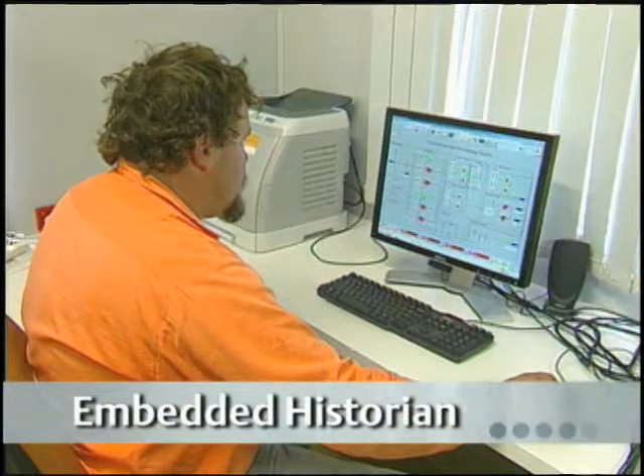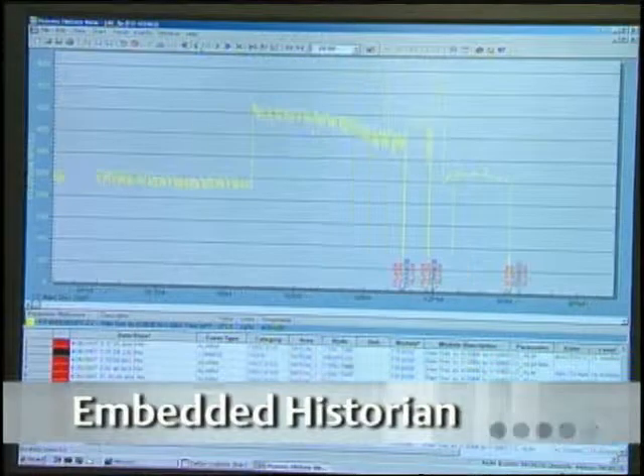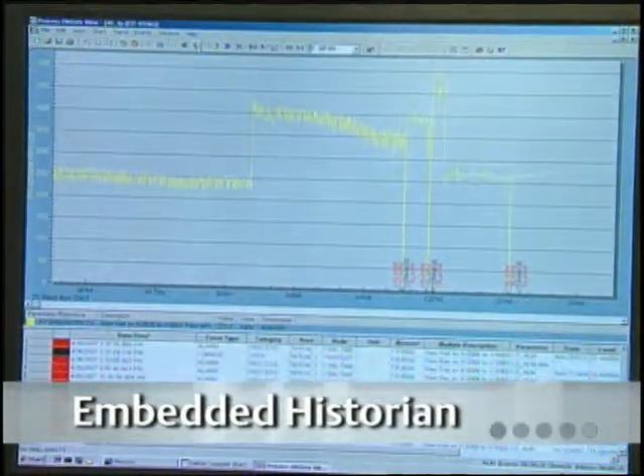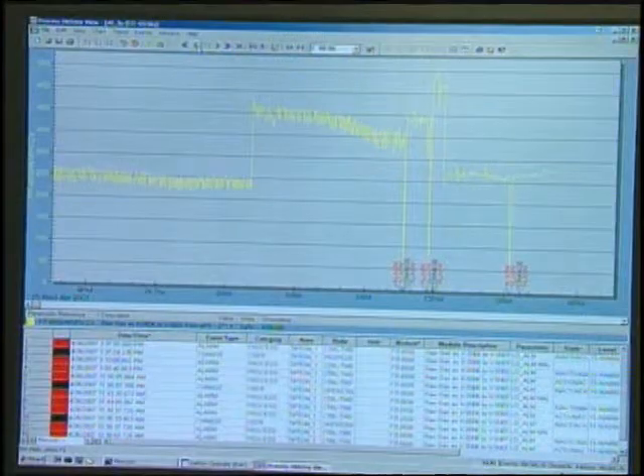All of our testing transferred through to real operations. With the DeltaV system it is handy with faults and alarms. Because it is a 24-hour operation, we might have a problem during the night, and you can trend that or go back into the system to find your problem and when it occurred — this helps greatly with troubleshooting and rectifying problems. So far through commissioning and the first couple of months of production, the product we've got from Emerson has done its job.